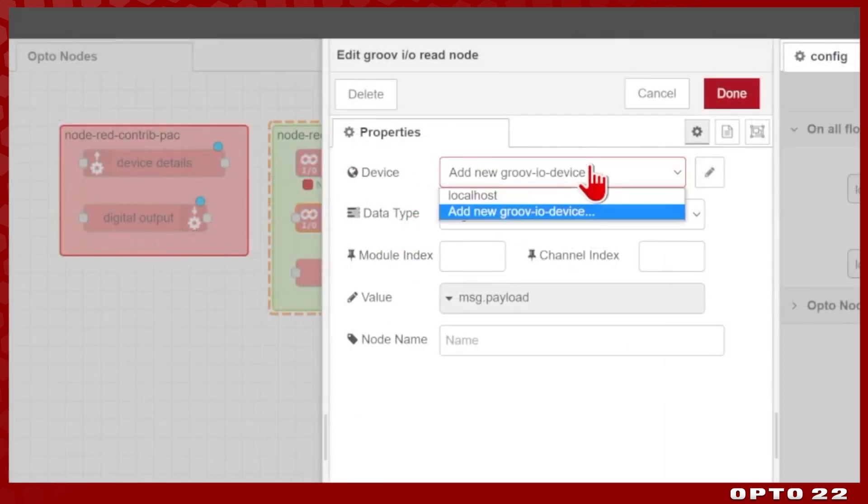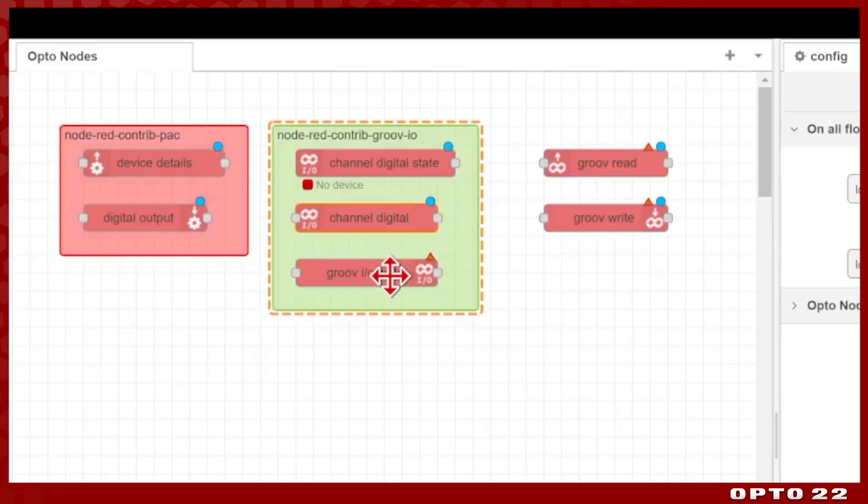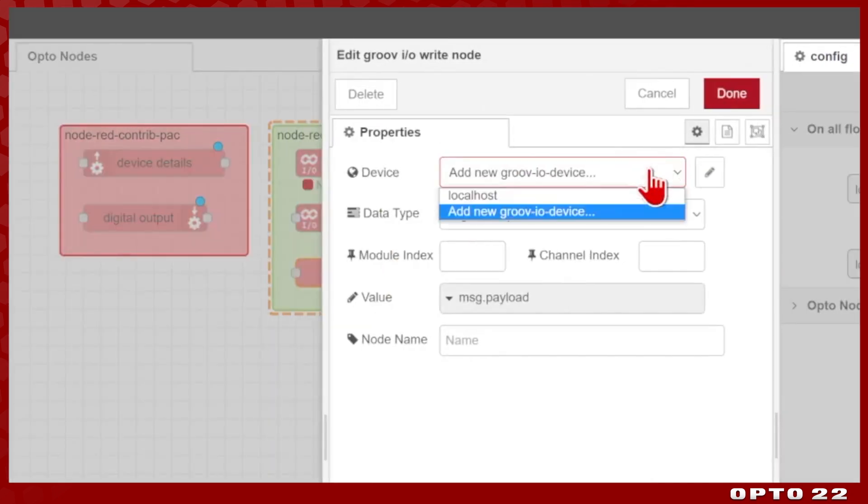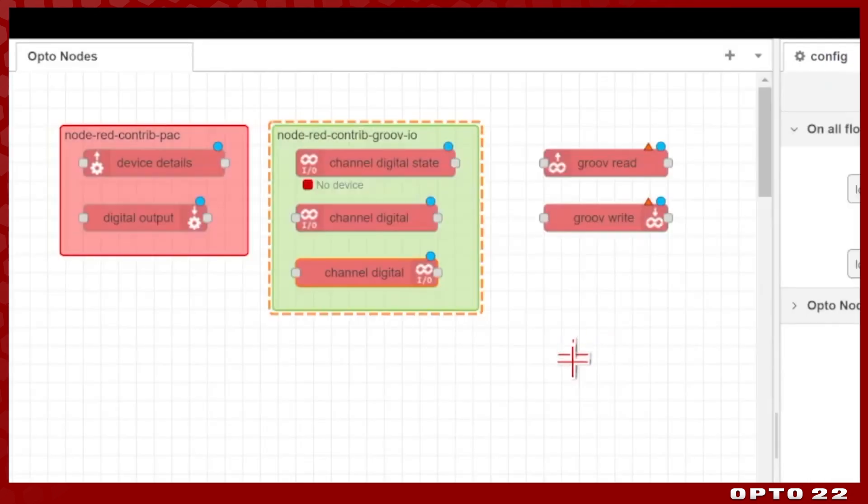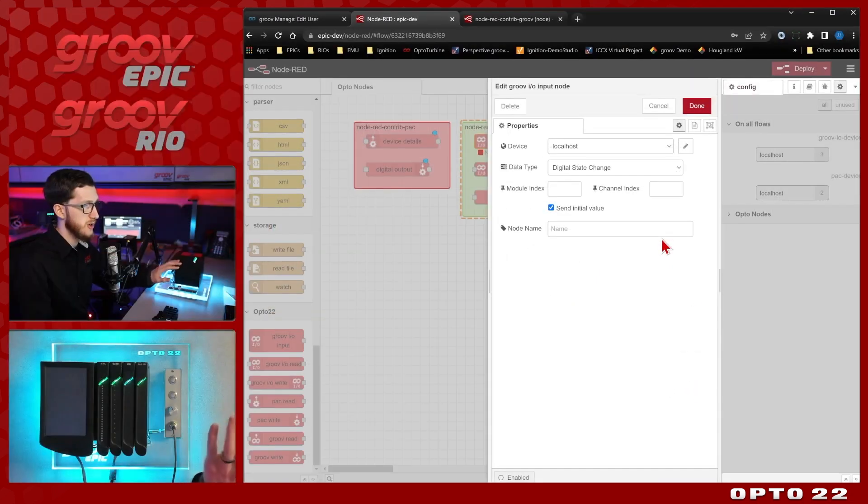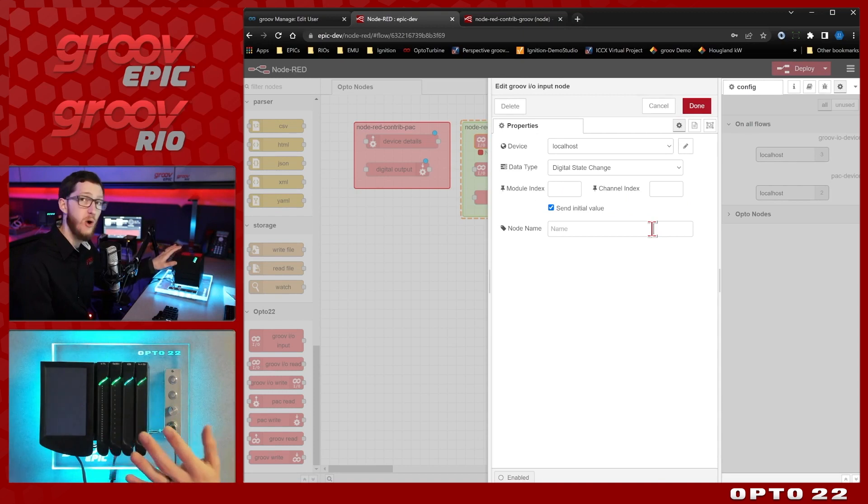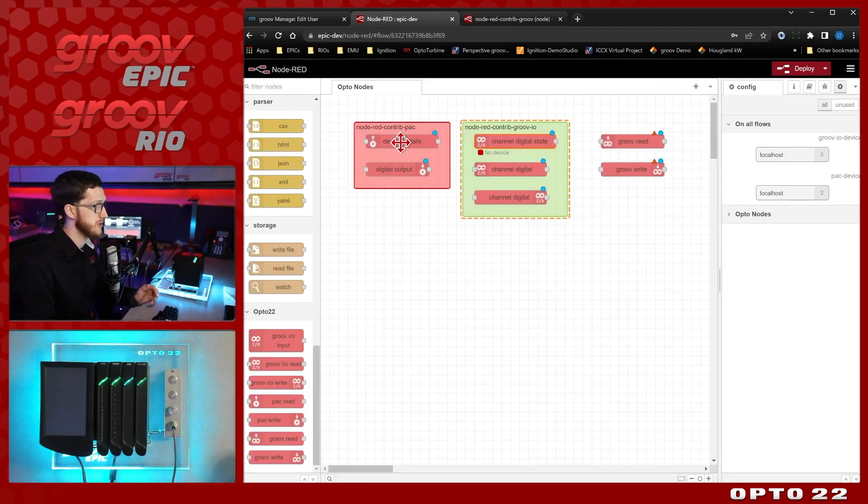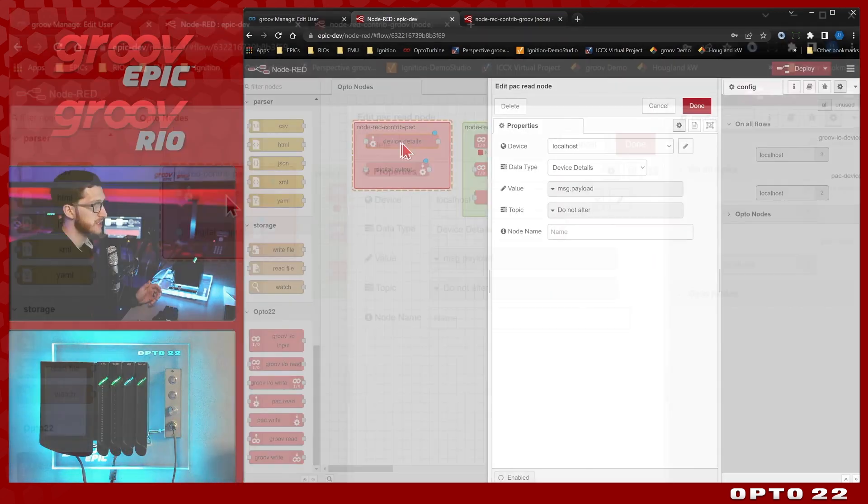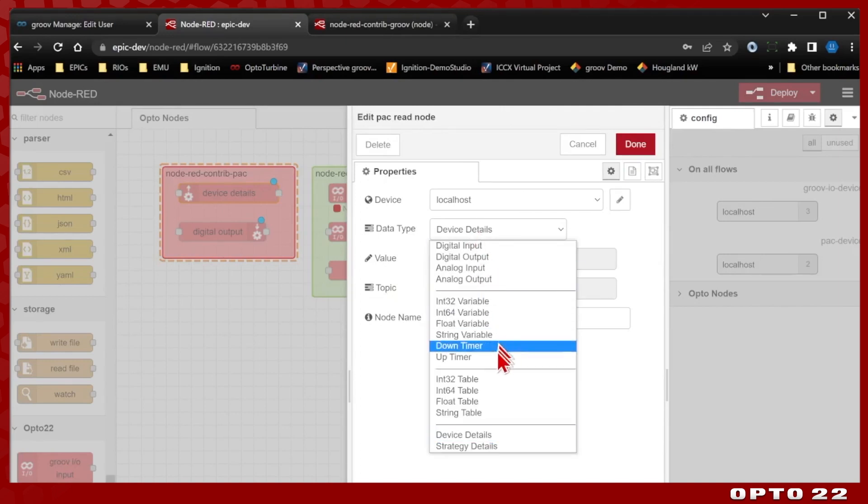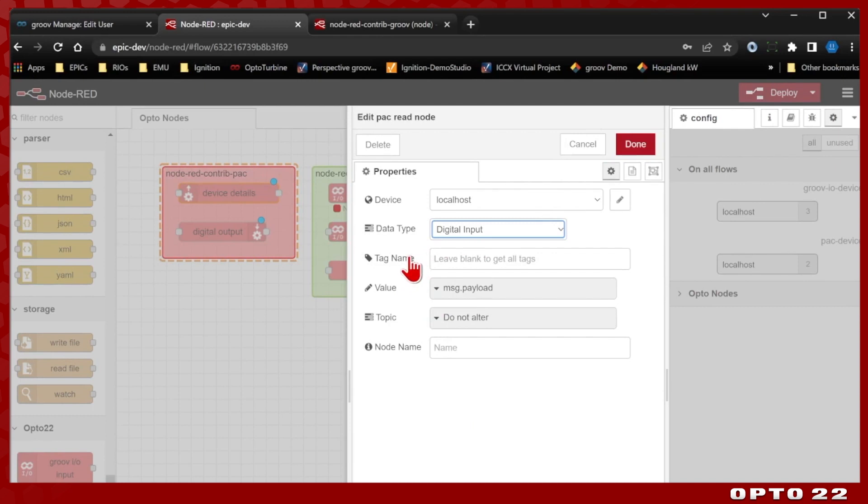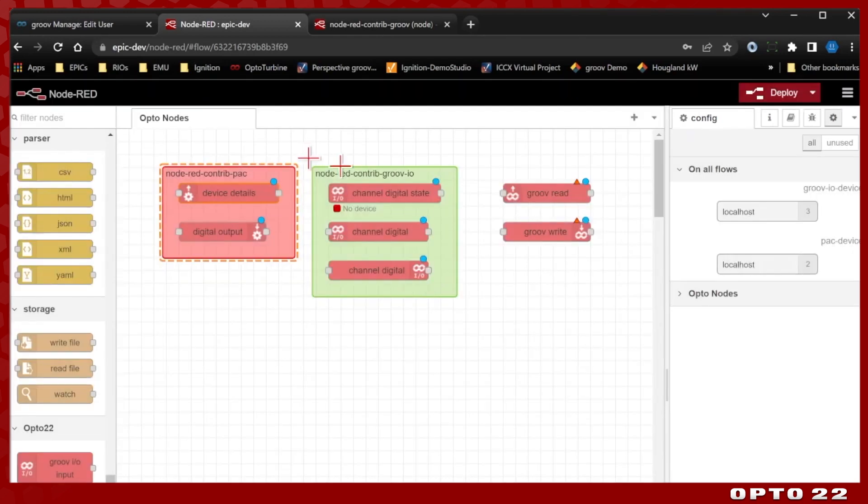I'll just apply this to all three of these nodes. And we're all set to go. You'll also note that the groov I/O nodes use the module index and channel index to reference the IO points. So this can be done whether you're running a PAC Control strategy or not. Whereas if you come over to the contrib-pac nodes, they instead use different data types. And if we select, for example, a digital input, it's going to be requesting the tag name. So it must be configured and made public in your PAC Control strategy. We'll go over that more in a future video. Just something to be aware of how these two packages are different.